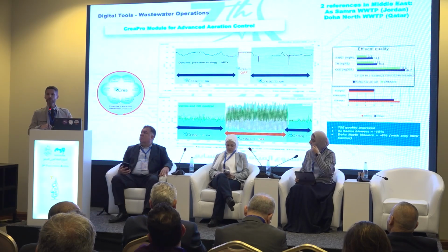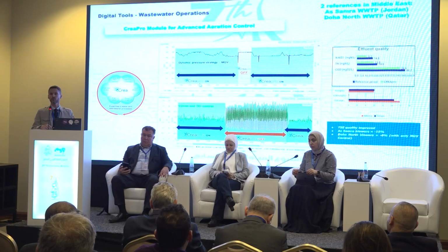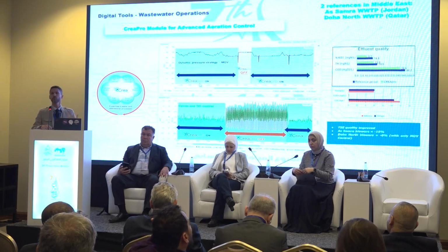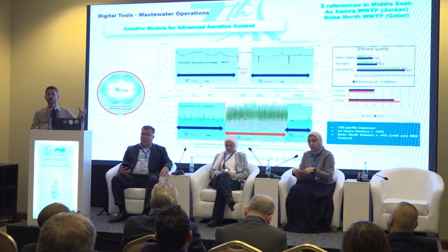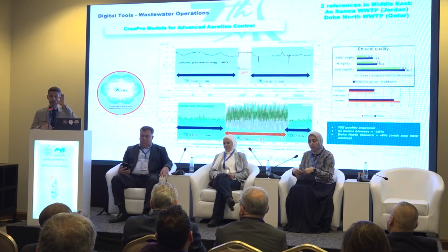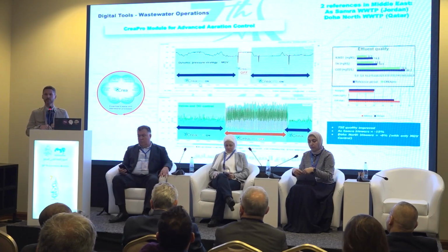We also have nitrogen and carbon modules that are using new sensors compared to usual. You put new ammonia and nitrates analyzers, and your system is capable of driving the plant according to these new parameters, to adapt to strictly what is needed for the oxygen, and then you are reducing your power consumption.